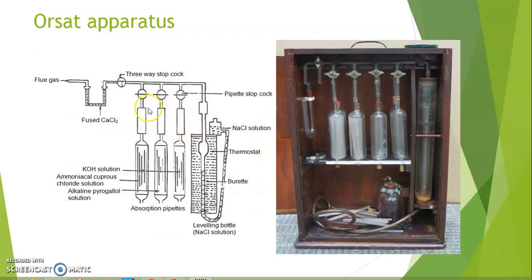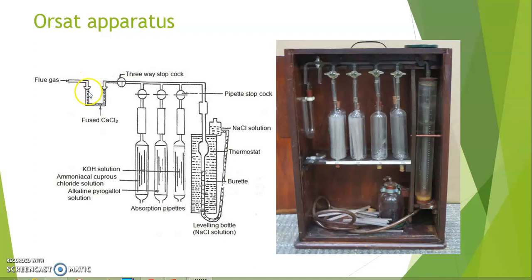The flue gas enters through the inlet. A calcium chloride guard tube is used at the inlet to remove moisture from the incoming gas. If there is moisture in the gas, it can interfere with the analysis. To avoid this, a stopper with calcium chloride is used to absorb moisture before the gas enters the absorption chambers.